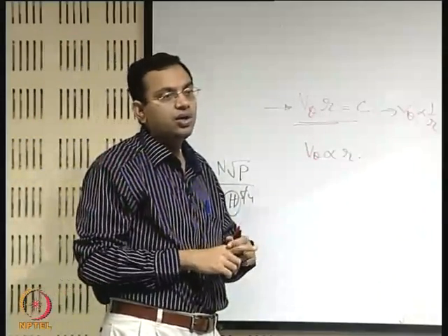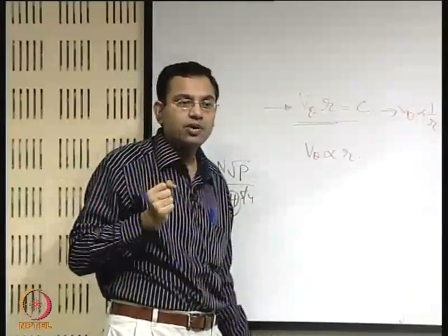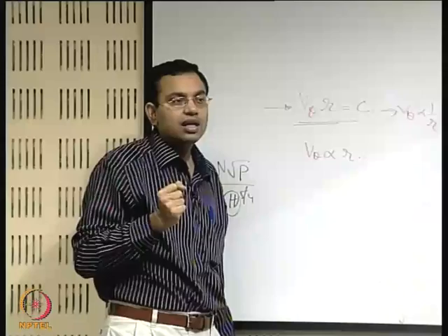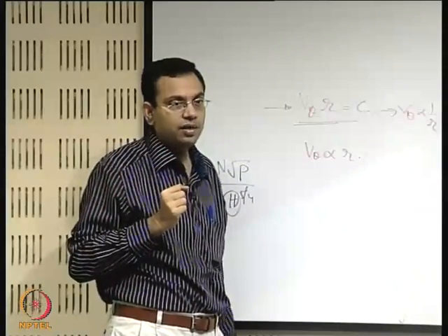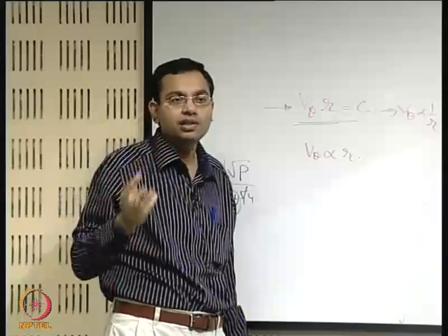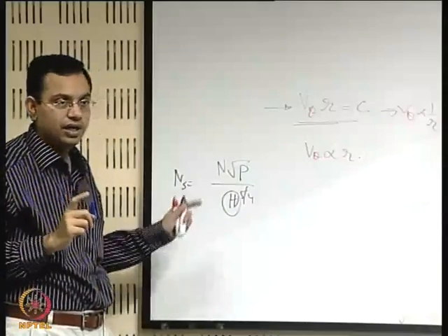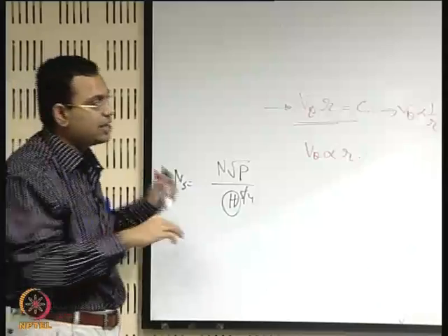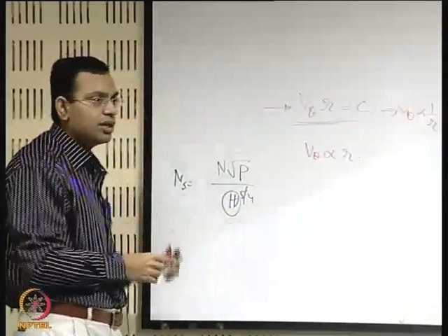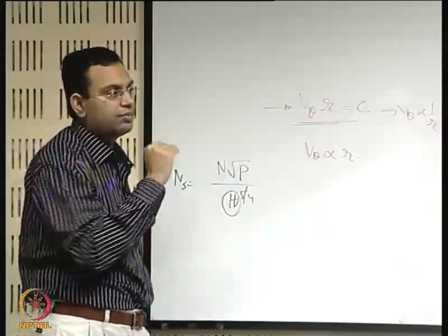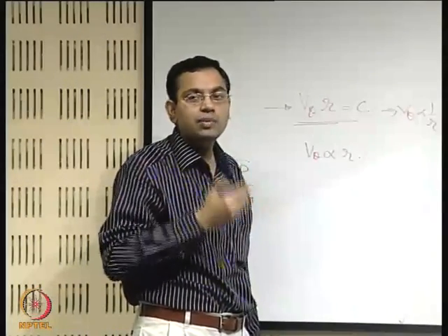On the other hand, look at the Kaplan turbine. The Kaplan turbine is an axial flow machine, and we have seen that it may operate on the basis of a high discharge but not on a high head, because a high head may give rise to flow separation and a stalling type of situation. So it will be operating on a low head. And the Francis turbine is sort of midway between these two behaviors. So we may conclude that the lowest specific speed out of these three will be the Pelton turbine, and the highest will be the Kaplan turbine.